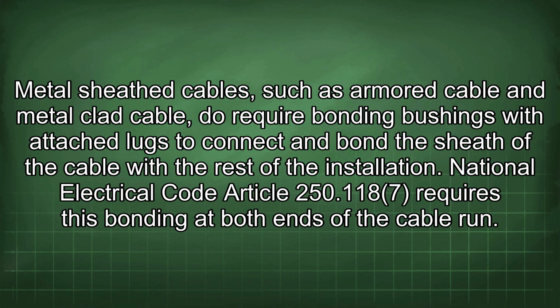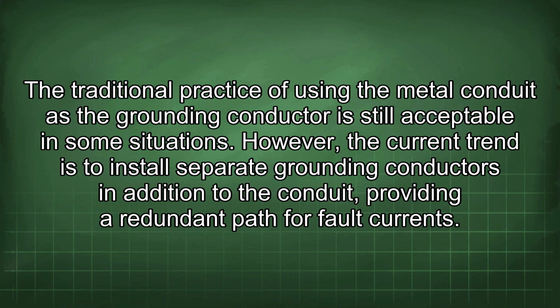National Electrical Code Article 250.118(7) requires this bonding at both ends of the cable run. The traditional practice of using the metal conduit as the grounding conductor is still acceptable in some situations.